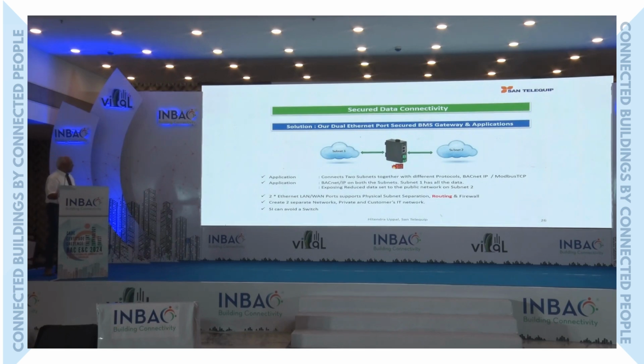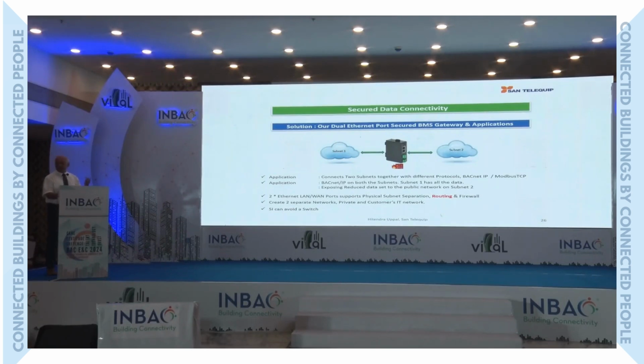So we have come up with a design where we offer two physically isolated Ethernet ports. On the first Ethernet port, you connect all the customer's network, with a router built in. The other port is absolutely safe - you can run all your BMS applications and give as many fixed IPs as you want, but you're completely isolated from the IT network. IT would see only the information it needs, because we have a router built in. So it's absolutely secured, because it's physically separate.